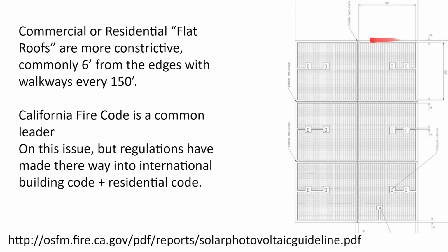You have to be 6 feet from the edges rather than 3 feet from the edges, because presumably you're walking around on this flat roof. You don't want to trip and fall over the edge because you're walking 3 feet from the edge.